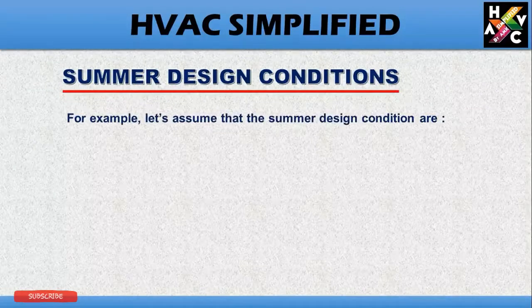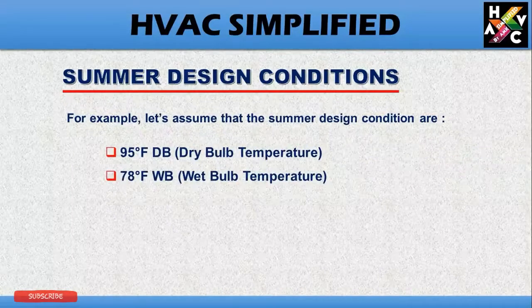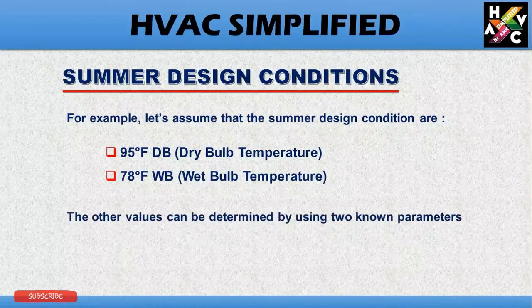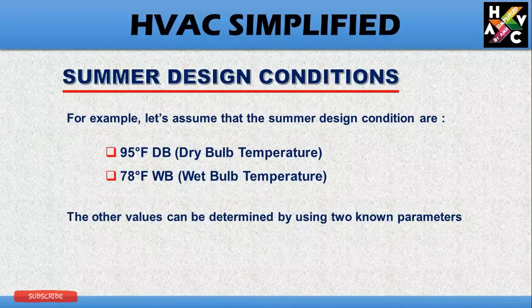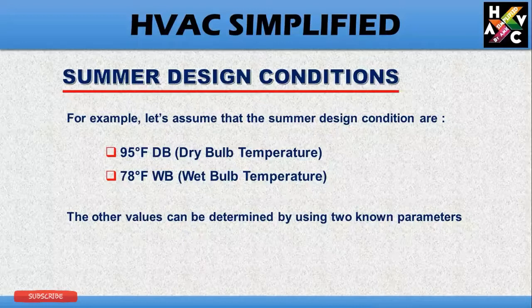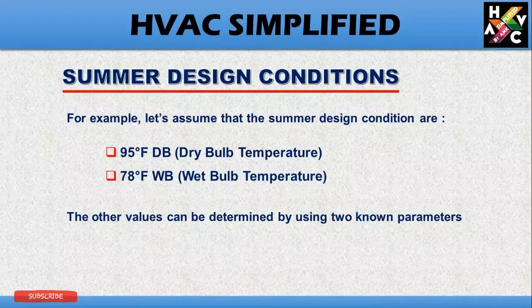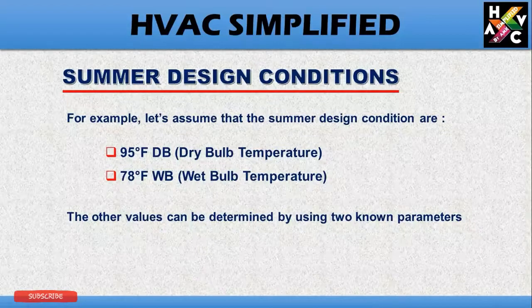Let us understand by using a few examples of summer design conditions. For example, let us assume the summer design conditions are 95 degrees Fahrenheit as the dry-bulb temperature and 78 degrees Fahrenheit as the wet-bulb temperature. The other values can be determined using these two known parameters. The basic concept of the psychrometric chart is to determine all parameters by using any two given parameters.